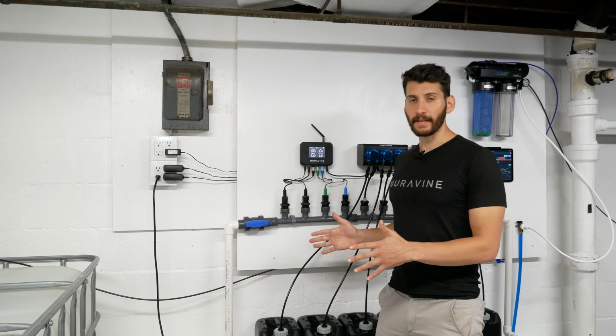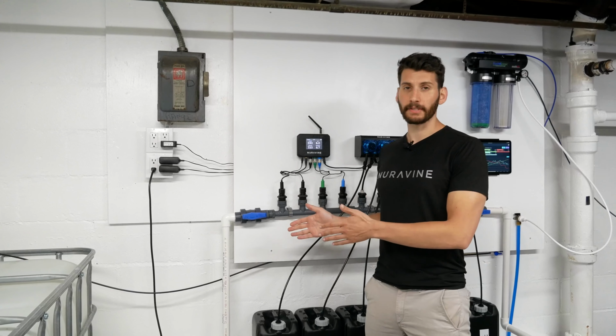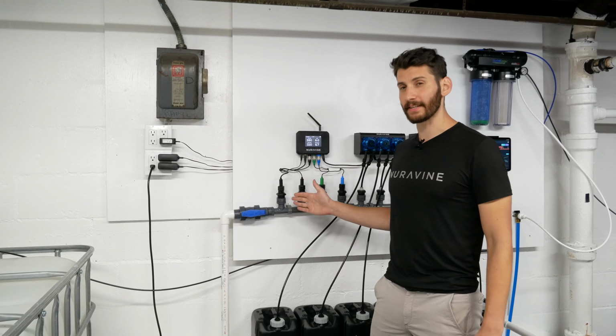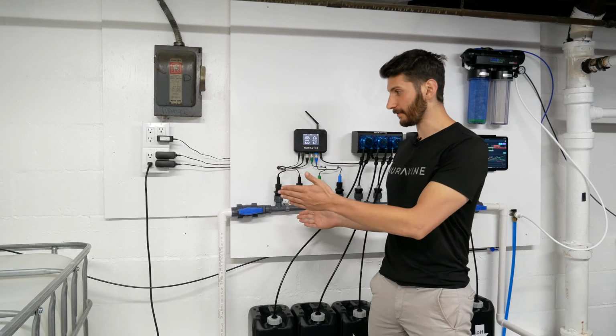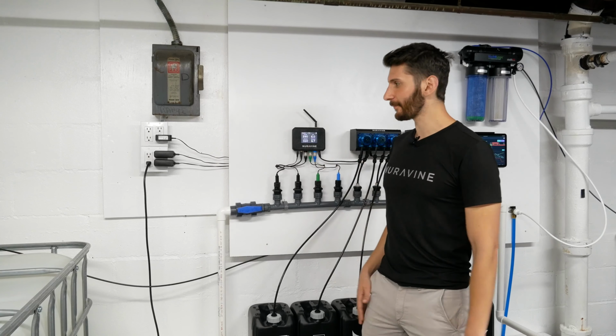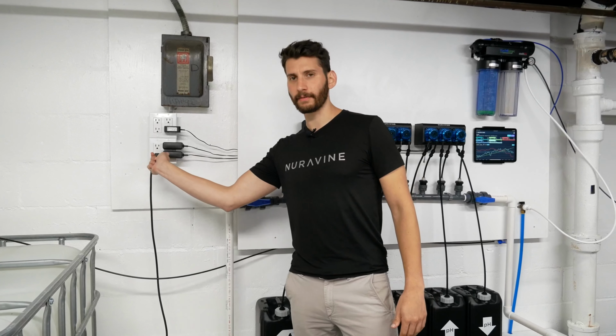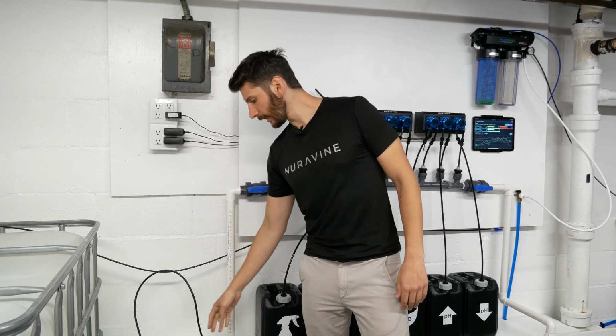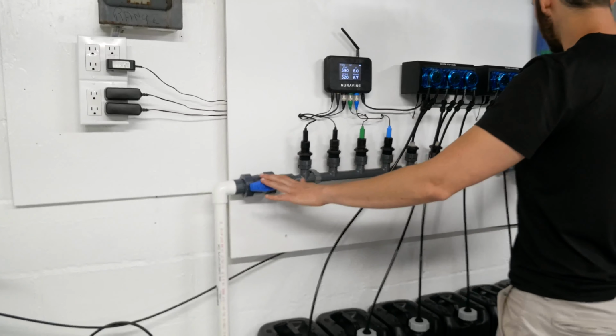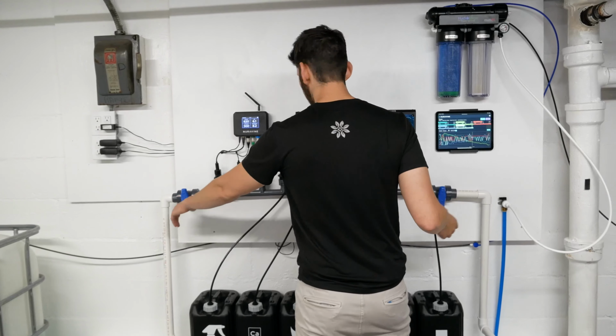Okay, so before we begin, it's important to turn off your system because we're going to have to take the sensors out of the manifold, and if we don't turn off the pump, water is going to come flying right out. So I'm going to unplug my pump right from the wall, and then I'm going to turn these 2 blue ball valves so this section is isolated.